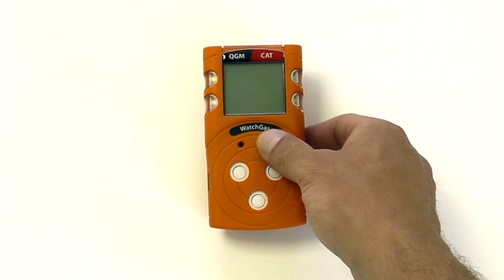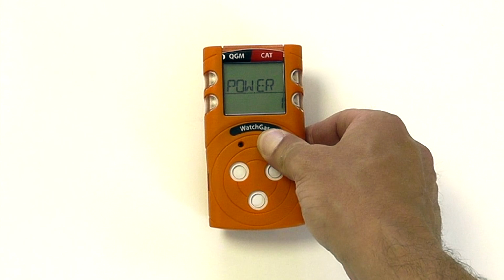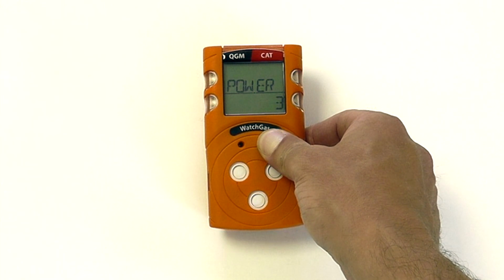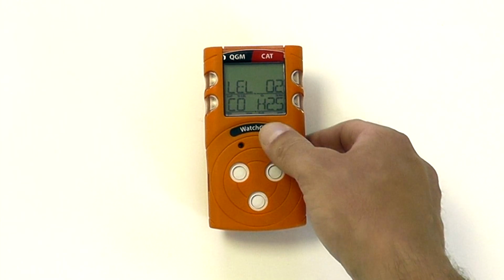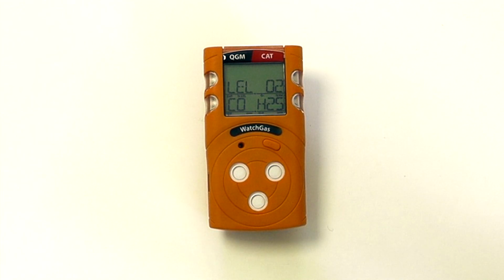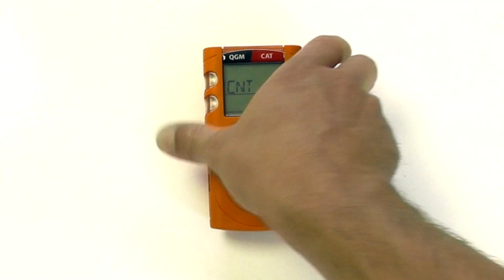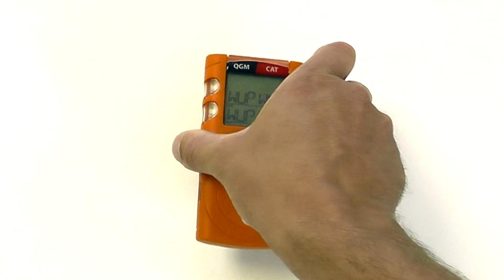To begin with, you can turn the instrument on: press and hold the button, 3, 2, 1. The unit will power on and go through its standard startup process. As we can see, we've got a 4-gas monitor here with LEL, O2, CO and H2S. We have instantaneous warning and danger alarms as well as STEL and TWA alarms. There's a full event history available within the unit for data download via the integrated infrared port on the top.